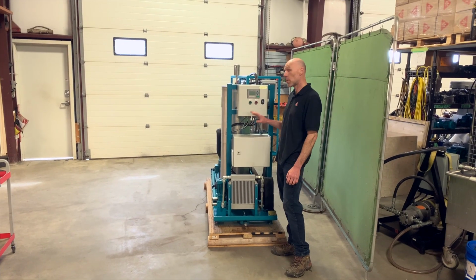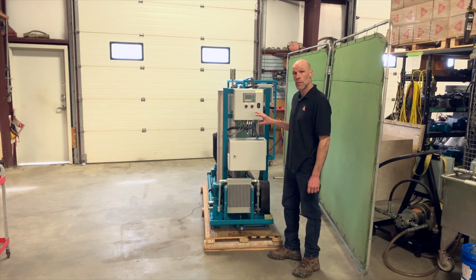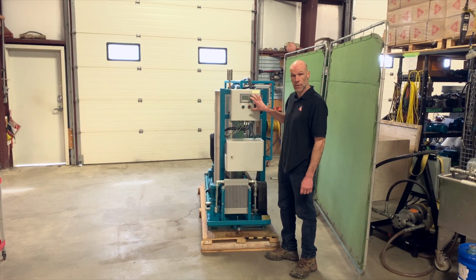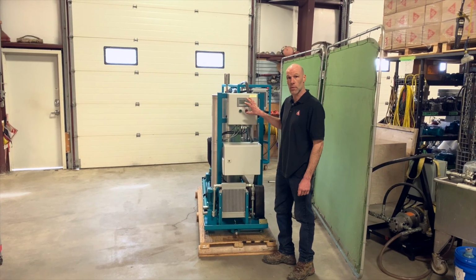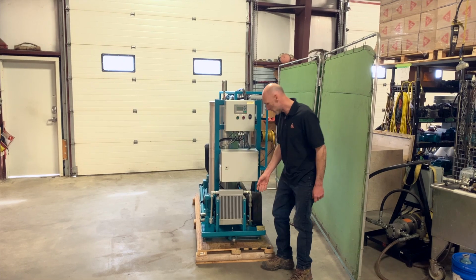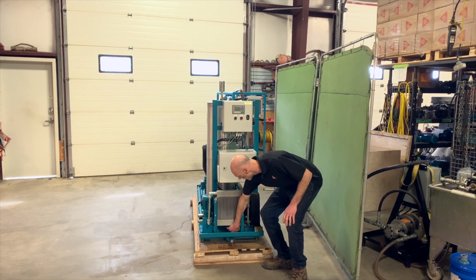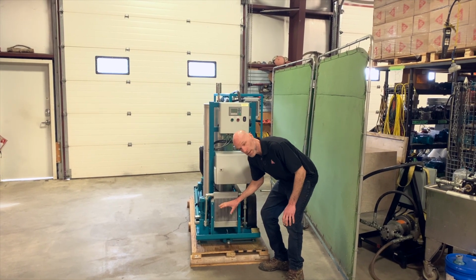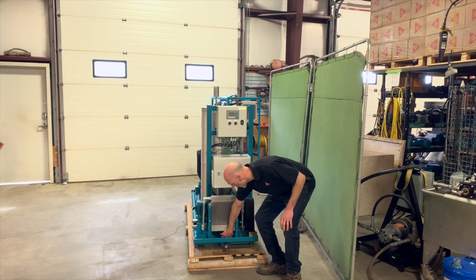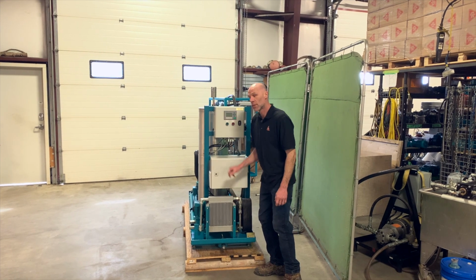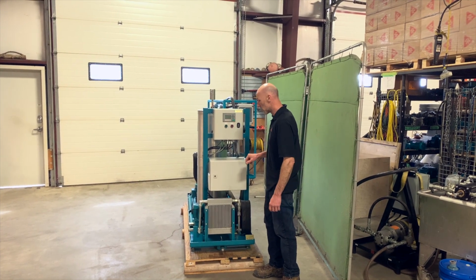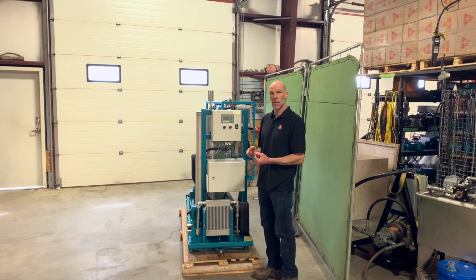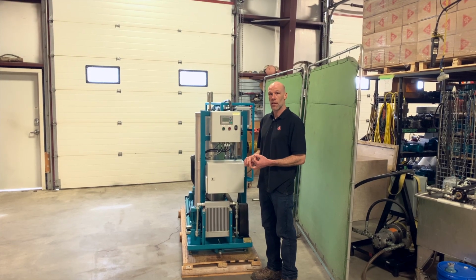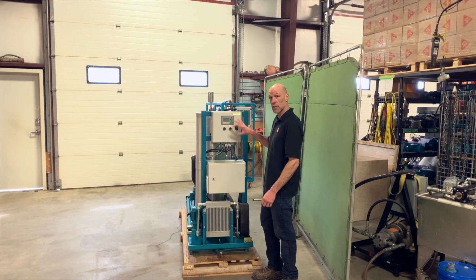The VRU has a number of safety features built into it, and they will be indicated on the screen if there's ever a fault or an alarm. One of the ones that's obvious to see is a spill switch down here. So if there's ever a leak on the system, it's going to fill in the pan and trip this switch. So you'll see that on the panel. There's also alarms for pressure, for temperature, and for a number of other things that are built into the logic of the system.